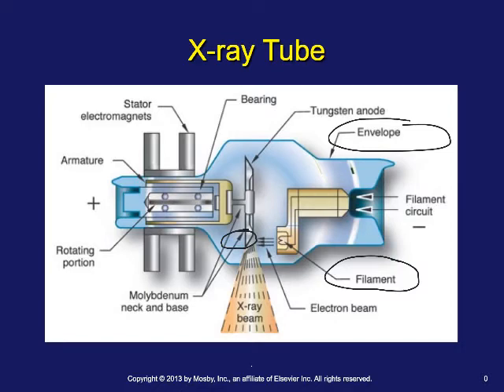The electrons are accelerated across the space from the cathode to the anode because of the potential difference between the negative and positive charge. They jump and accelerate very quickly across the vacuum, slam into the anode target, and in the process produce x-rays as well as a whole lot of heat. Most of what the x-ray tube produces is heat, infrared light, and visible light — the anode will literally start to glow white hot, which is one reason why we rotate it rapidly.